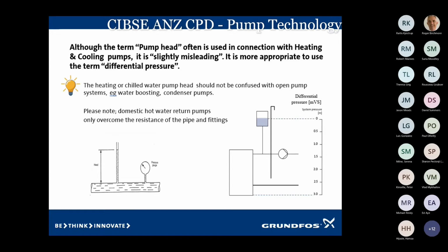overcome. So in an open system, 10-story building, we're pumping water through into showers to taps. We need to measure the height of the building, the losses through the pipework, and the losses through all the fittings. Whereas if it's a heating system or a chill water system in a 10-story building, all we need to do is overcome the losses in the pipework, the fittings, and the units that we're connecting to.